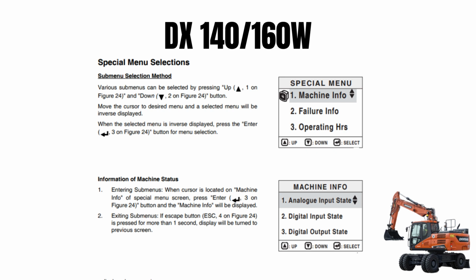Let's suppose I want to choose this machine information sub menu. I will bring the cursor onto machine information and press enter. After pressing enter, you can see in the bottom screen there are 3 categories displayed against machine information: analog input state, digital input state, and digital output states. So to enter sub menus, when the cursor is located on machine information of the special menu screen, press enter, and machine information will be displayed. If you want to exit these sub menus, press this escape button for more than 1 second, and the display will be turned to the previous screen of special menus.